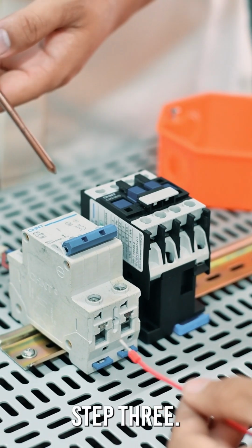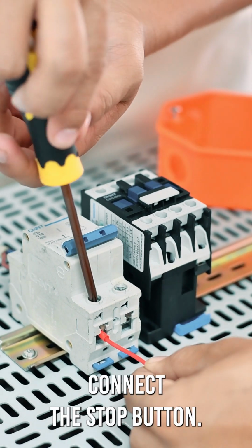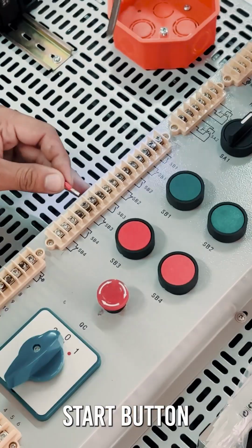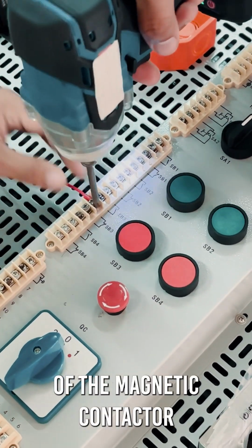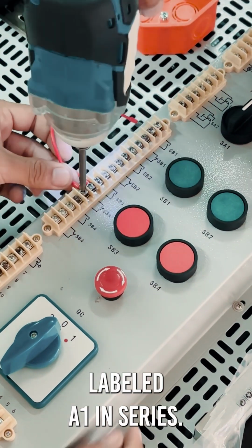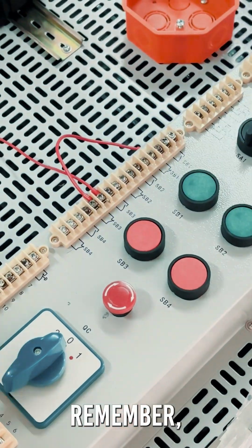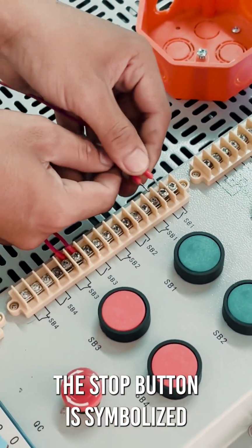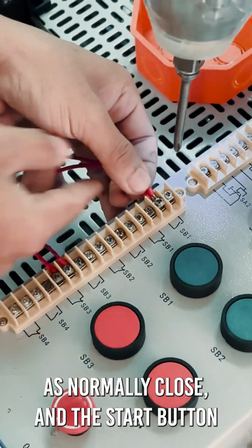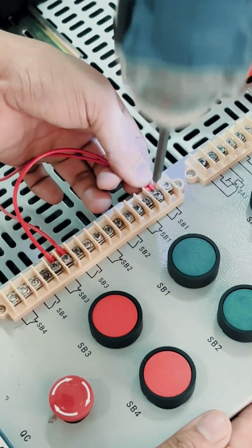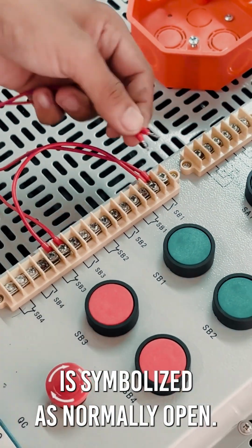Step 3: From the live wire, connect the stop button, start button, and the coil contact of the magnetic contactor labeled A1 in series. Remember, the stop button is symbolized as normally closed, and the start button is symbolized as normally open.